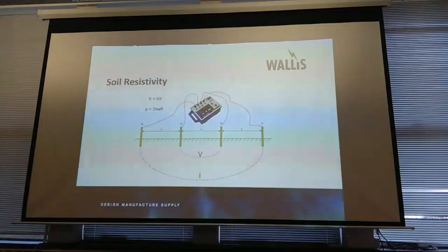So if you're ever on a site and you've got some guys, be it us, be it one of our competitors, come out, that is what we're doing. We're sticking probes in the ground. Through the outer two probes, you're injecting a fixed current, milliamps, nothing great to it. And through the inner two probes, you're measuring the voltage. From that, you get very simple V equals IR, which gives you the apparent resistance. You then do a little formula: rho equals 2 times pi times A times R. A is the distance between the rods, R is the resistance from the meter, and that gives you the actual resistivity of the ground at that depth.